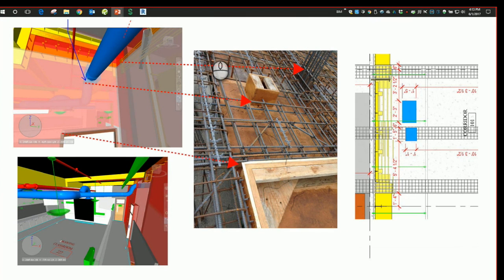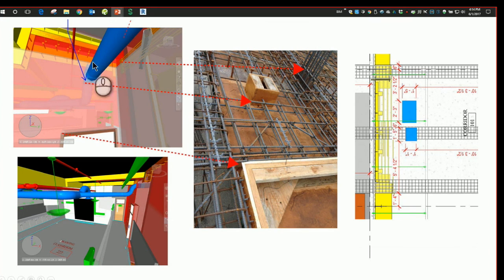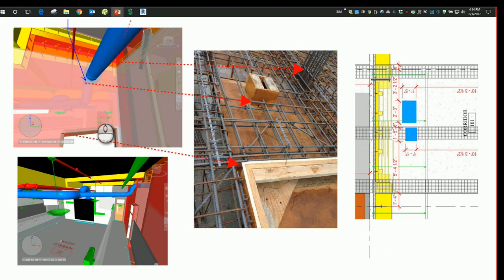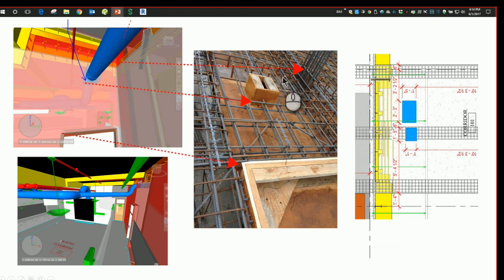As the walls were being formed and rebar was being put in these walls, we know that existing conditions or conditions in the field require us to move and adjust things at times. Therefore, as we laser scanned these, it enabled us to go back to our 3D coordination model with the mechanical, electrical, fire sprinkler trades and have them make those adjustments to their coordination model prior to fabrication. So that when they came out to the field, they found these openings precisely where they had anticipated them and had fabricated for them.